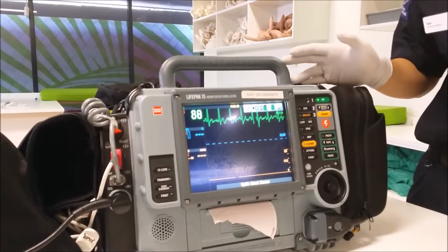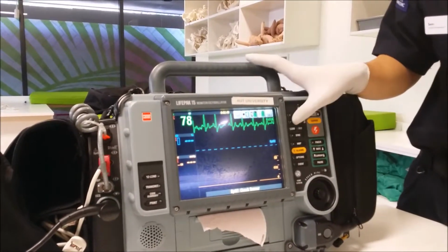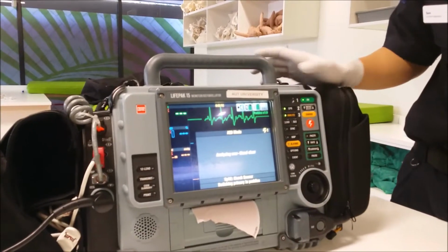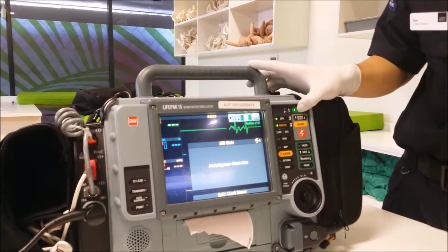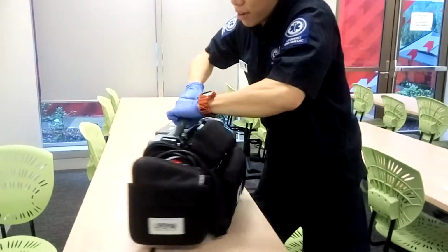So for our final check, we just want to put it back in AED mode, and you do that by pressing the Analyze button. Analyzing now. Stand clear.